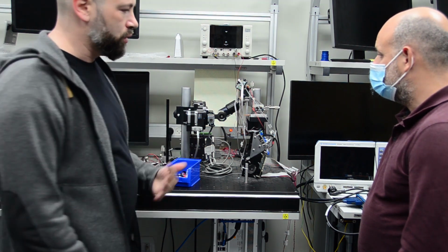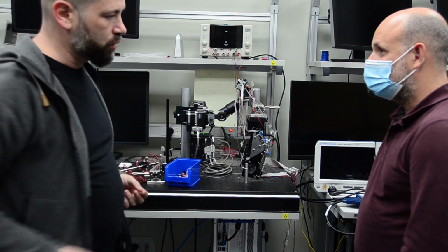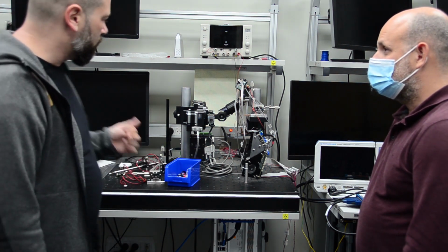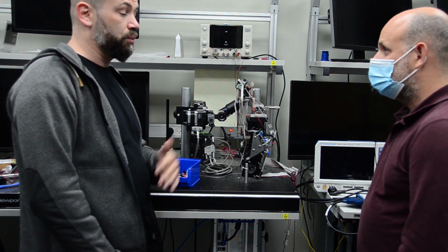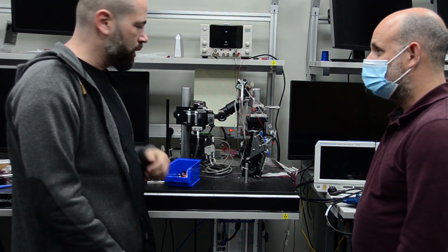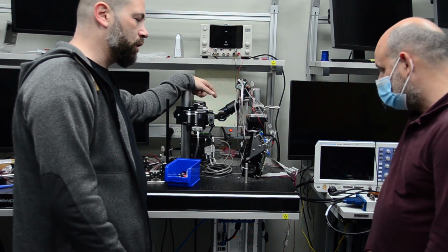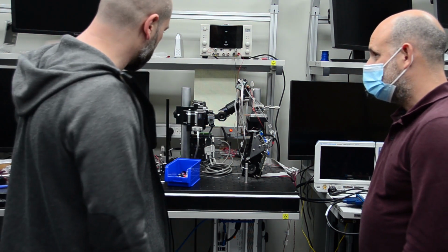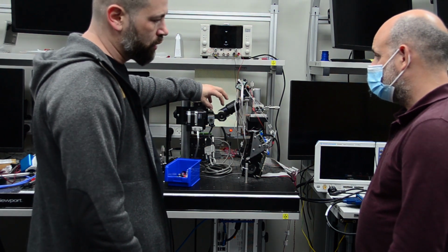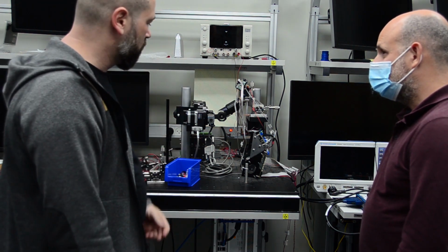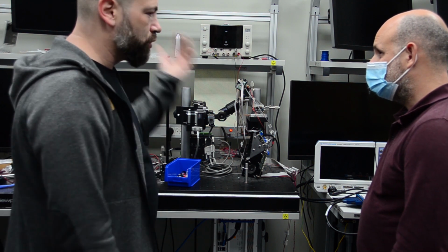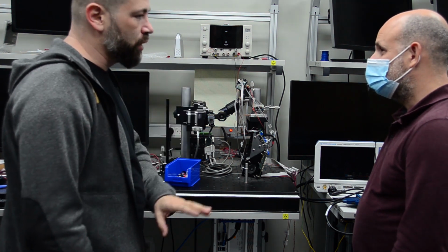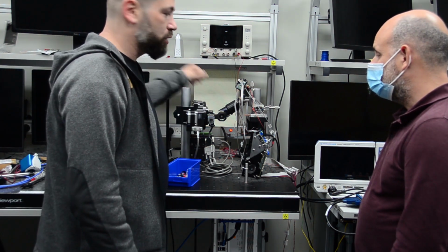Now, obviously, we need to operate it in such a way that the moment you put the glasses on, it finds the eye. So, in order to do that, we developed an algorithm that searches parameters of angles and lateral positions of the eye, in order to detect the position and do the initial close loop. So what we'll do now, we'll open the loop, as you can see now. Now we'll shift the eye to some angle, and then we'll try to close the loop. We press the button. Now we will demonstrate it in demo mode, which means that we deliberately slow down the mirror. So you can see it does this spiral shape.